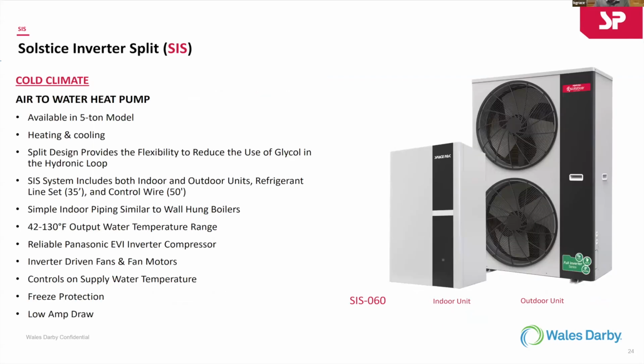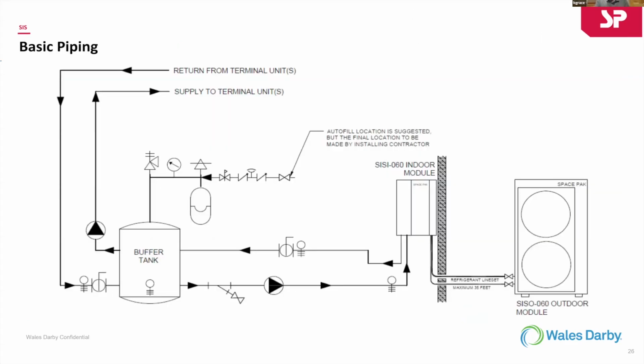So again, the split system could be a place where, like I said, with Arctic temperatures you may not want to have the water go outside, even with glycol. It's so cold that you just don't want it. You could bring this inside. Or even here in New York, where space is a problem or logistics of getting things in and out, it might actually be easier to put the unit outside, put the tank in the basement, and run a set of refrigerant lines to it. Again, this is what it would look like. It's just feeding a buffer tank, and the buffer tank then feeds the system.